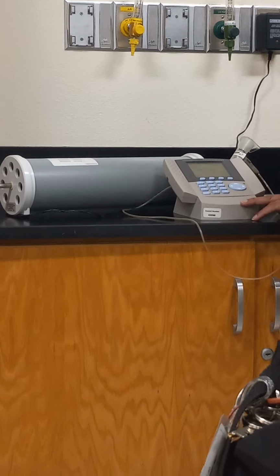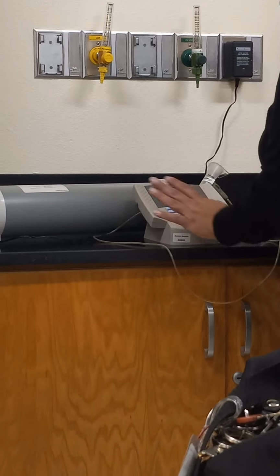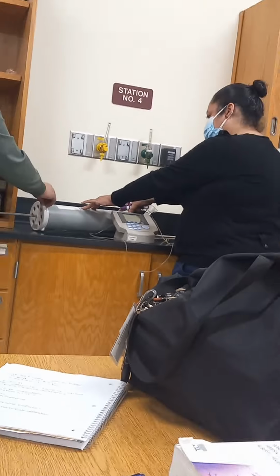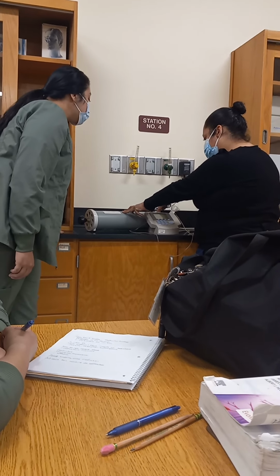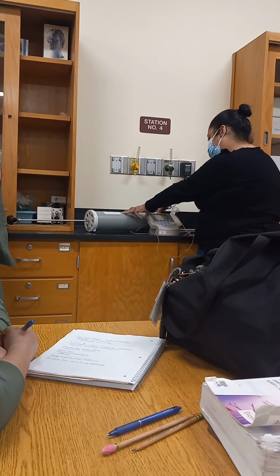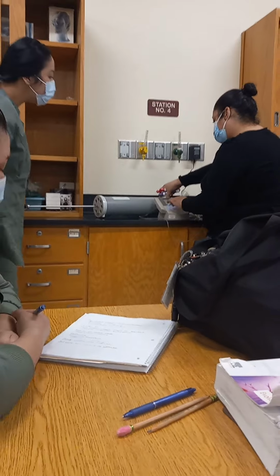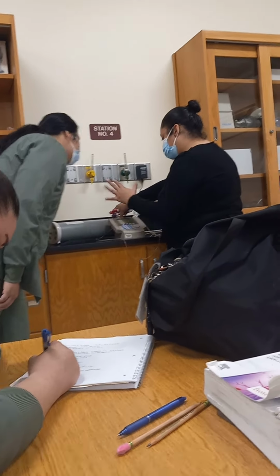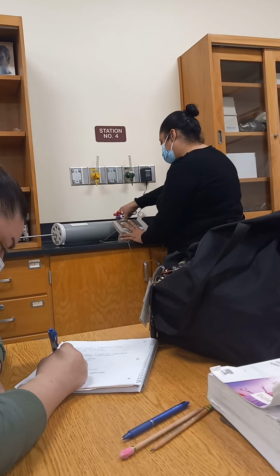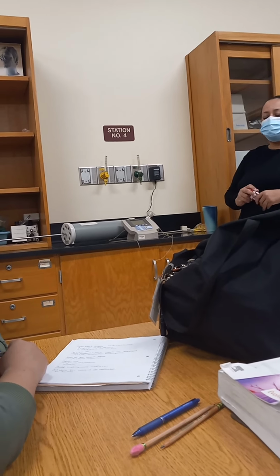I think it gave it to us, right? It was really fast. Zeroing. Go ahead and push it in. Okay, go ahead. Here's your inhale and exhale, so that's a good difference. We've already done our cal check. It's less than 3%, so we can trust it.